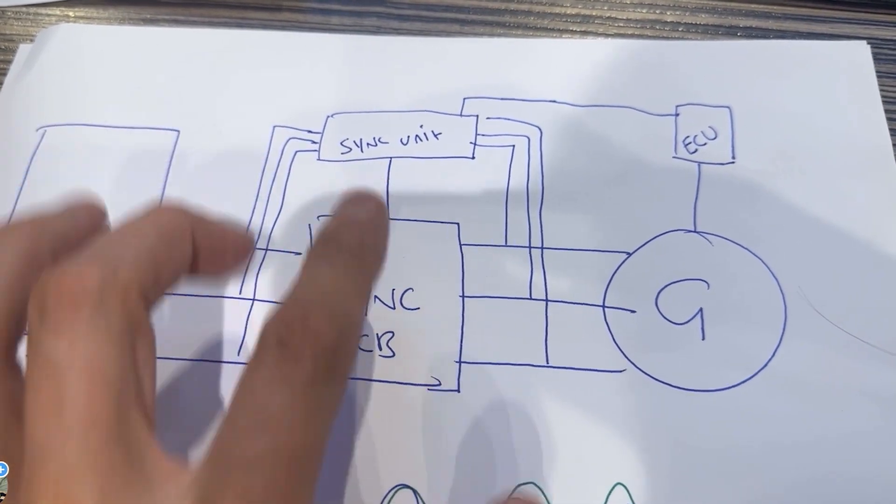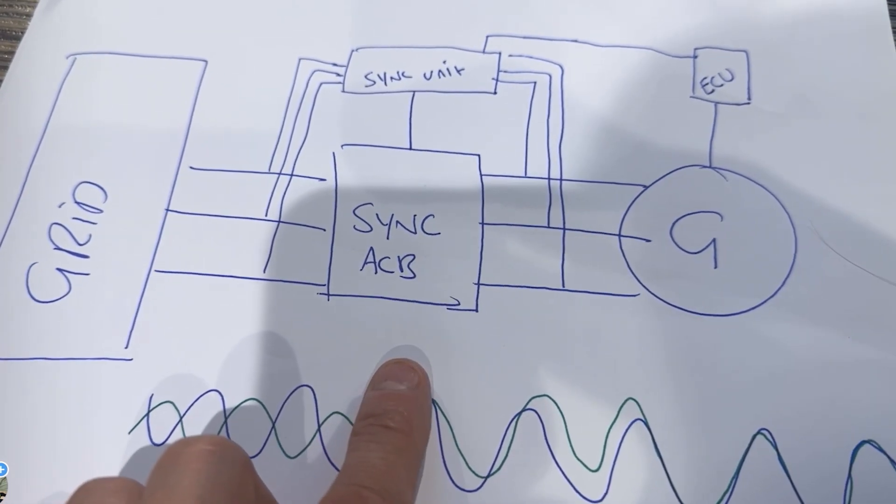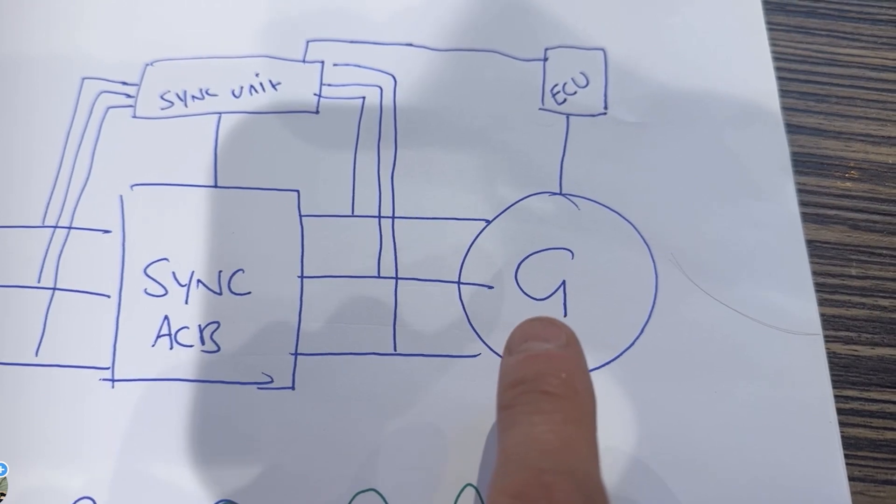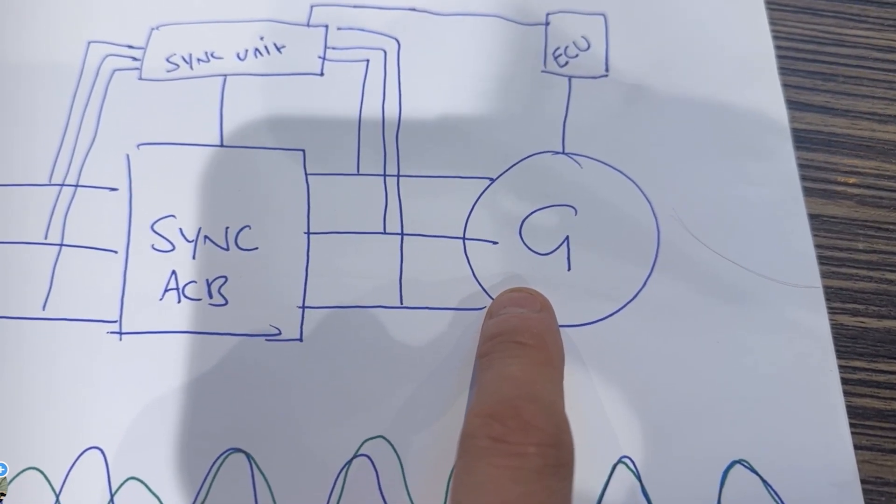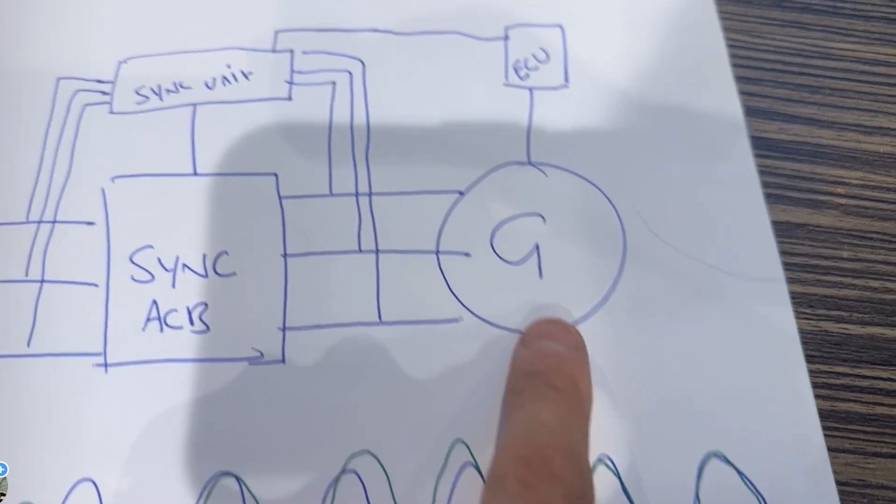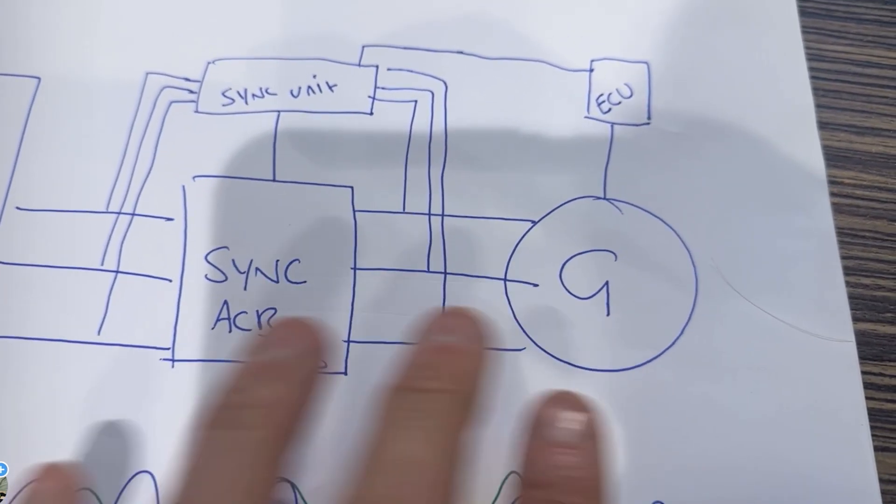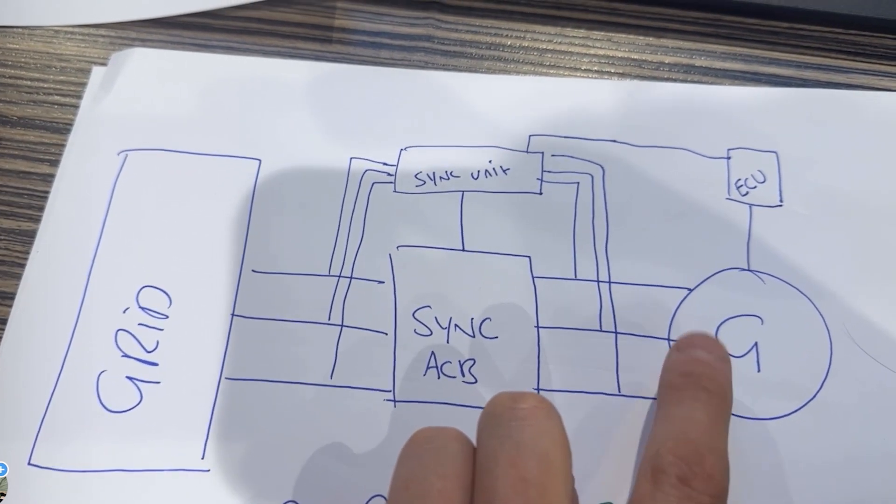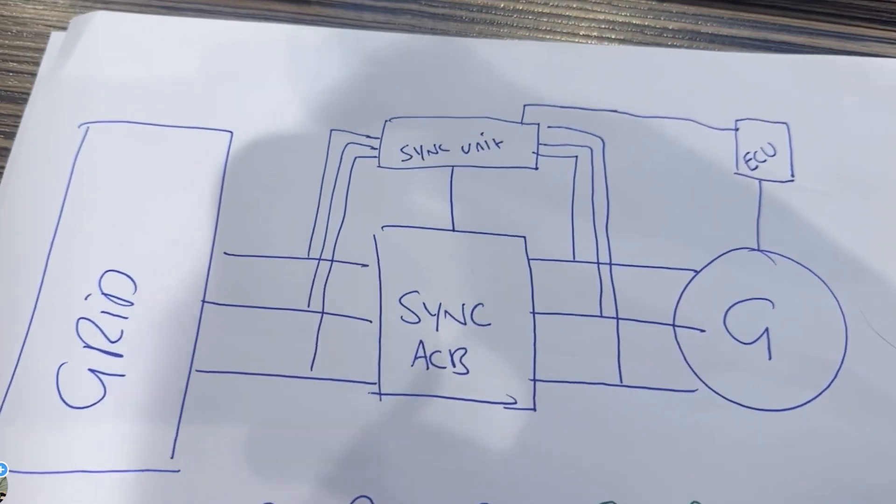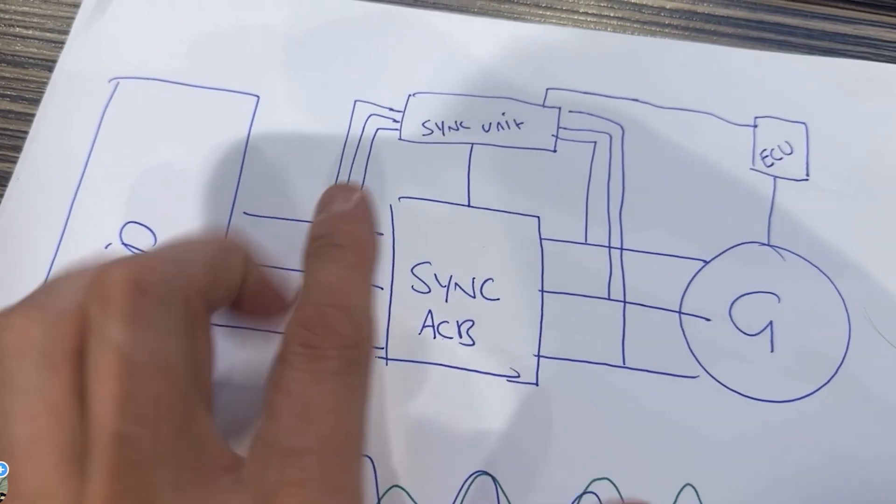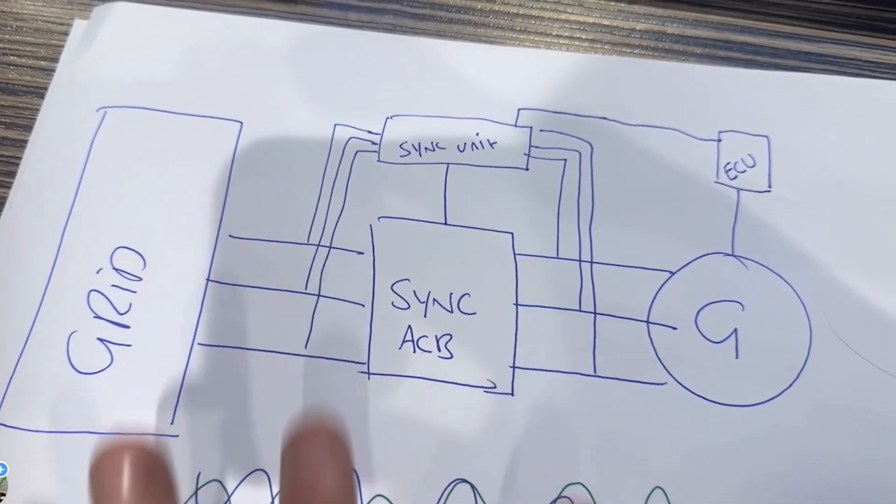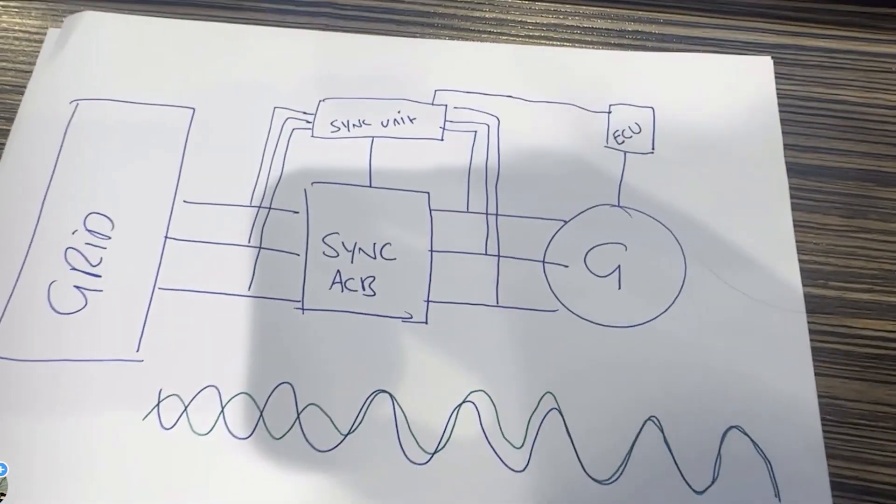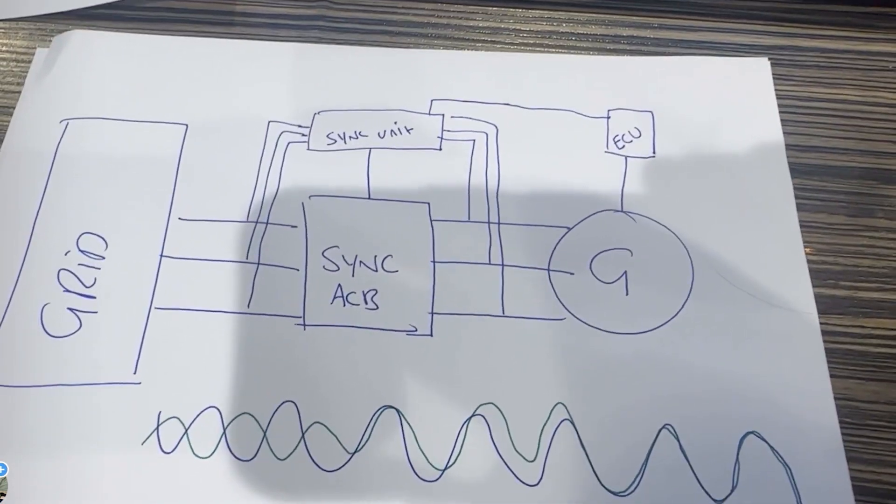But if something mad happens like you take the generator away and put one back and it's going backwards, the sync unit will just see that and go no there's something wrong. If the grid tries to move the generator, the sync unit will see that and know there's something wrong. This saves loads of different components but now it's an overall package. So that's when I refer to sync breakers, that's what I'm on about. It doesn't have to be a motor, it could be a solar farm I'm guessing. You still got to sync it. It could be a steam generator, a gas generator, turbine, anything.